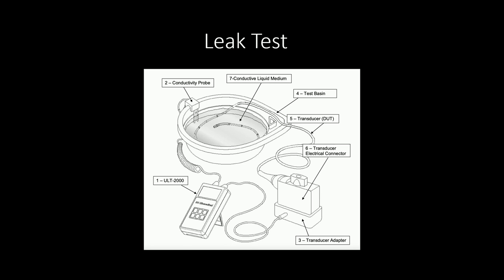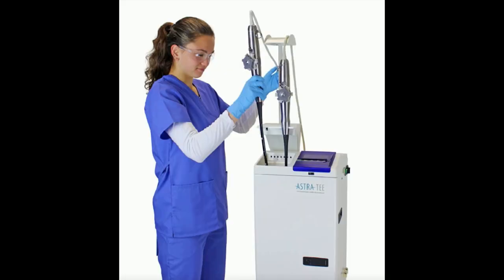So this is something you really have to have on your radar. Half the probes that come from central supply, we just told them at one point, don't just send them back up. Put a note in them that it failed, and then we'll just deal with it. Because our cardiology department says we just use them because they all say they failed the leak test. So I don't know what that means. I don't know that anyone in our hospital has ever been shocked by an ultrasound probe, but something to think about. Tim, you were saying the same thing happens at your place, right?